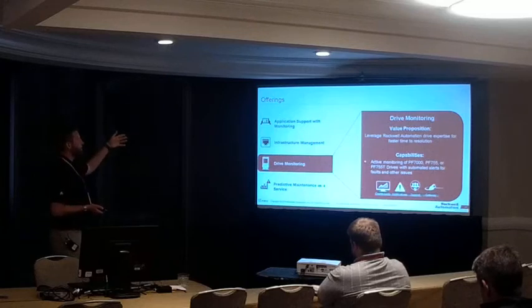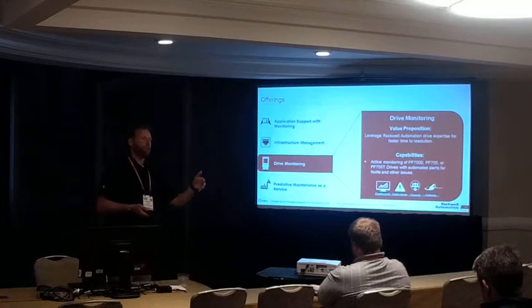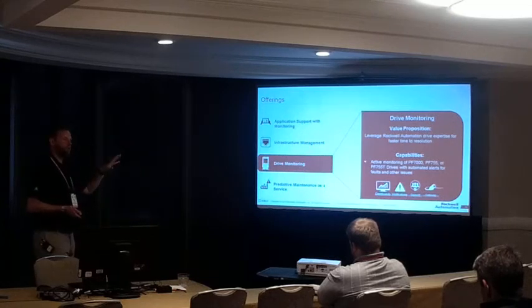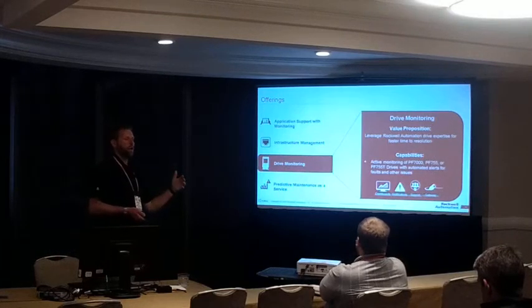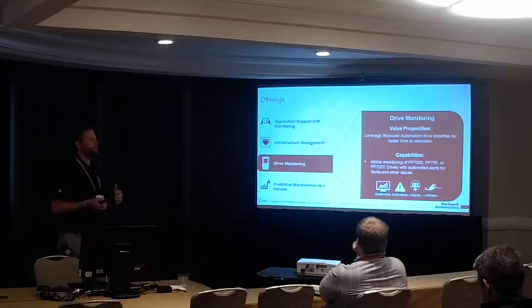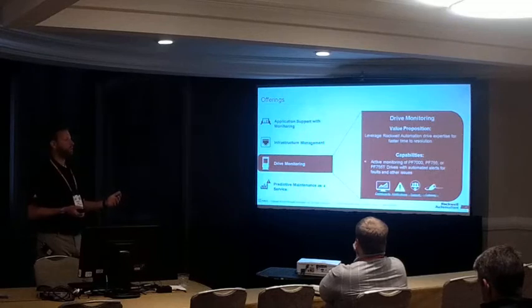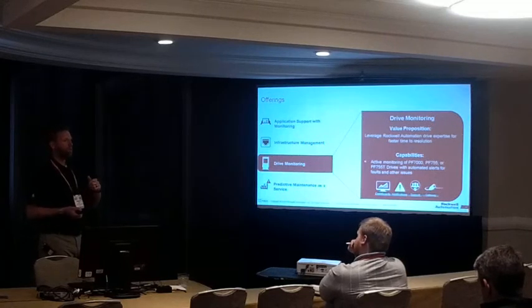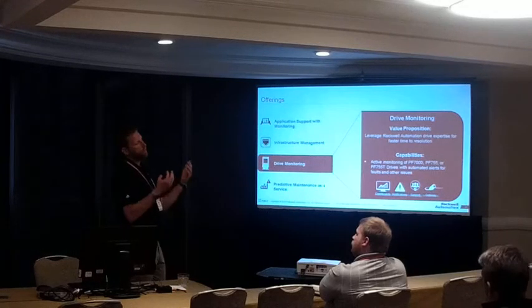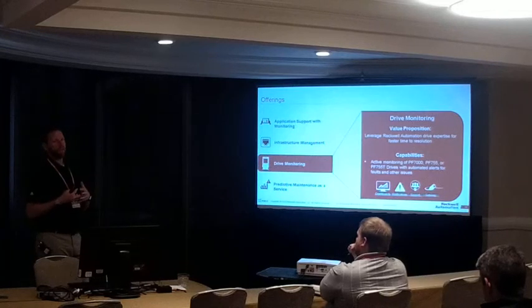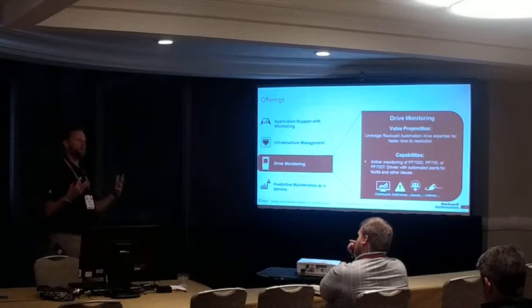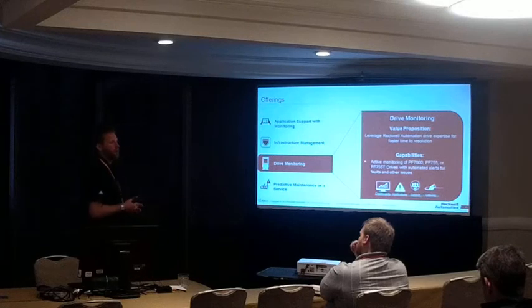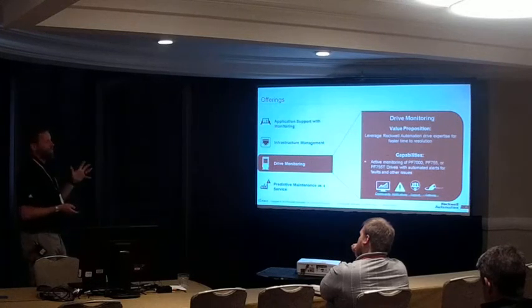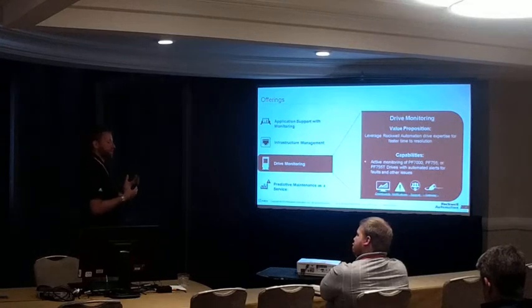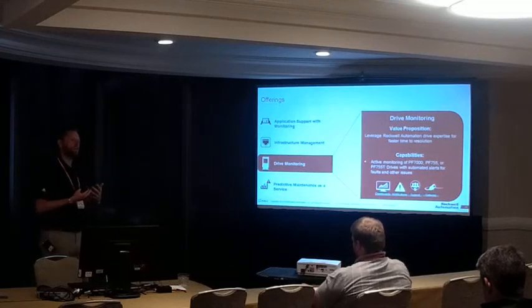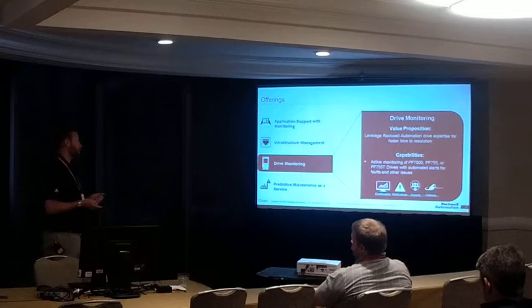Drive monitoring is kind of a focused flavor of application monitoring, where we've built specific dashboards, alerts, and alarms around various models of Rockwell Automation drives. The goal is we've got support engineers who are experts on those drives sitting in a command center, watching the screens, waiting for alarms to trigger, and proactively calling customers to say, hey, we're seeing this fault, let's troubleshoot how to resolve it and move on. So we're supporting those drives remotely, reducing the requirement for customers to have that technical knowledge to troubleshoot them. They're getting very complex and are in very critical applications, so any downtime is expensive. Typically, at least half of the issues we've seen with drives are sympathetic to the overall application, not an issue with the drive itself. So helping manage and troubleshoot where that issue lies is of value to customers.